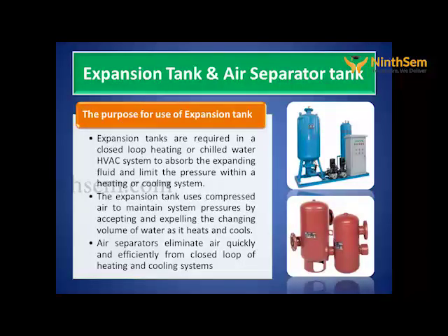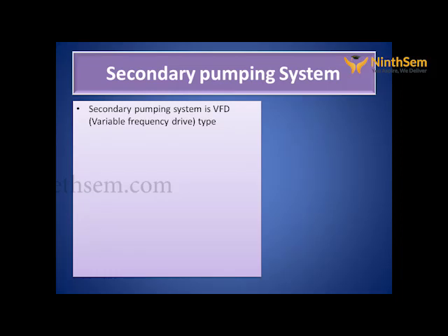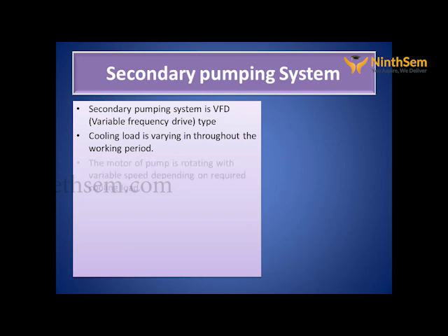Air separator basically eliminates air quickly and efficiently from closed loop of heating and cooling system. Now, secondary pumping system. Basically, secondary pumping system is VFD type, as cooling load is varying throughout the working period. The motor of the pump is rotating with variable speed depending on required cooling load.